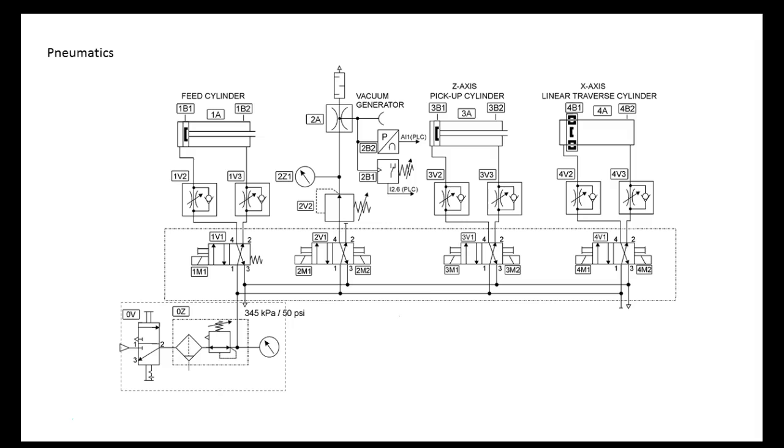Now, why do we meter out? Because if you meter in, you understand, the air hits that cylinder, the cylinder moves, the air uncompresses, then it's got to compress again, then it moves, then it uncompresses. So if we meter in on pneumatics, the cylinders would be real jumpy. But if we meter out, the flow control is trying to hold it, and it's always pushing against the pressure. So you get a lot smoother movement in pneumatics.